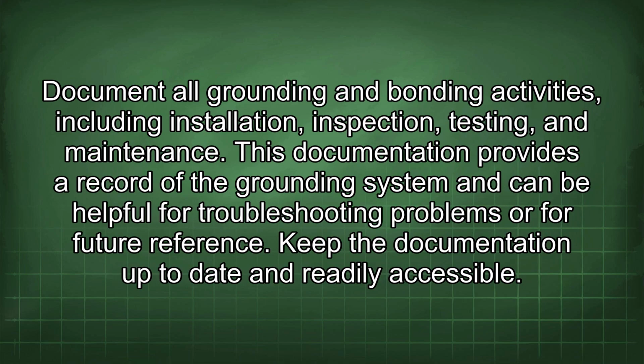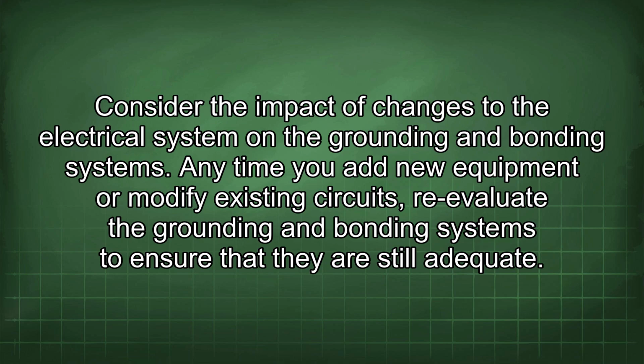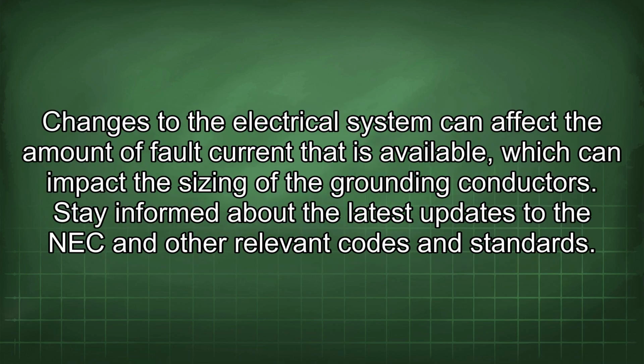Document all grounding and bonding activities, including installation, inspection, testing, and maintenance. This documentation provides a record of the grounding system and can be helpful for troubleshooting problems or for future reference. Keep the documentation up to date and readily accessible. Consider the impact of changes to the electrical system on the grounding and bonding systems. Anytime you add new equipment or modify existing circuits, re-evaluate the grounding and bonding systems to ensure that they are still adequate. Changes to the electrical system can affect the amount of fault current that is available, which can impact the sizing of the grounding conductors.